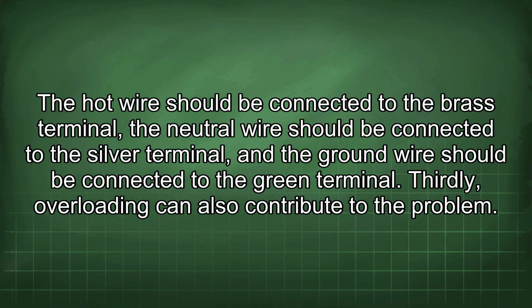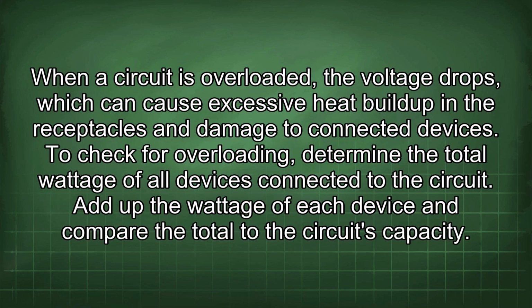Thirdly, overloading can also contribute to the problem. When a circuit is overloaded, the voltage drops, which can cause excessive heat buildup in the receptacles and damage to connected devices. To check for overloading, determine the total wattage of all devices connected to the circuit.